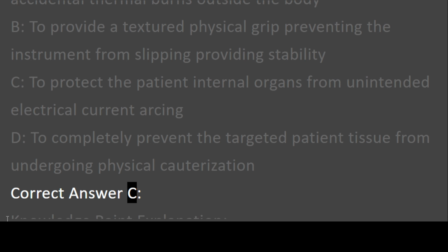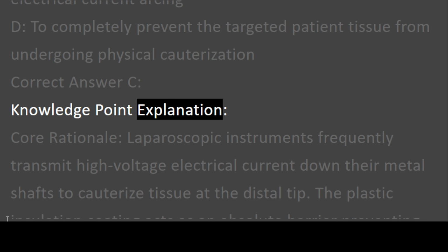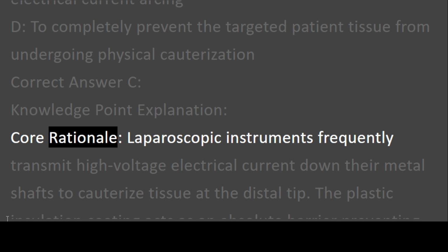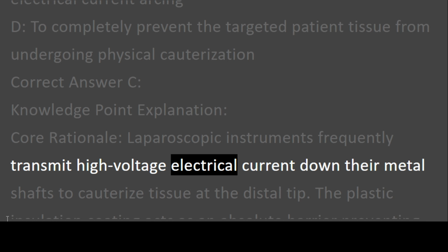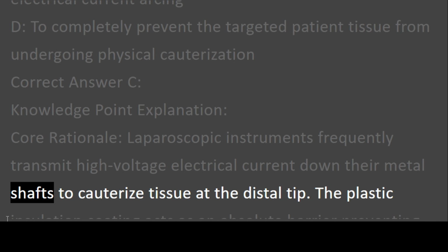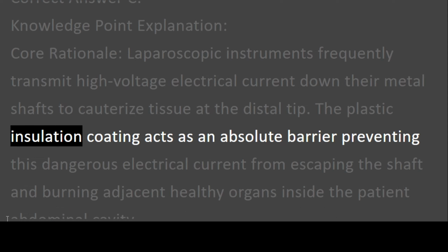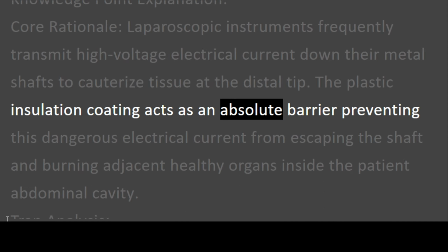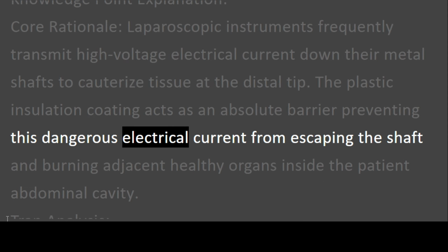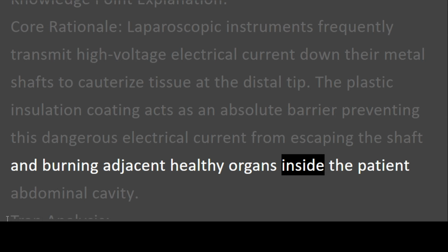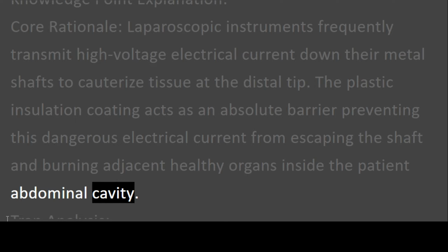Correct answer C. Knowledge point explanation. Core rationale. Laparoscopic instruments frequently transmit high-voltage electrical current down their metal shafts to cauterize tissue at the distal tip. The plastic insulation coating acts as an absolute barrier, preventing this dangerous electrical current from escaping the shaft and burning adjacent healthy organs inside the patient abdominal cavity.